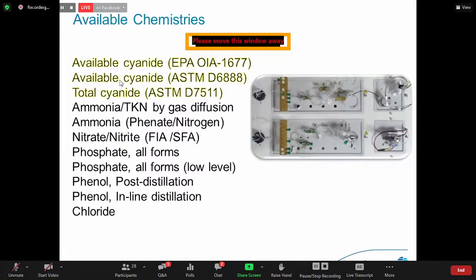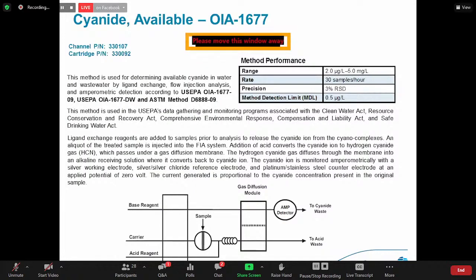So these are just some of the available cyanide methods: 1677 available cyanide, 6888, total cyanide by 7511. And these are some of the other ones, just a short list of some of the other ones that are available on the 3700 platform. And with each instrument, and I'll show a number of these, this is part of the abstract, we call it, from the laboratory methods. Excuse me. This gives the channel part number, the cartridge part number, the range, the rate, precision, the method detection limit for each method, a short diagram as we've seen earlier of how the instrument is plumbed, and then background on the method itself and which regulatory methods this is going to conform to.